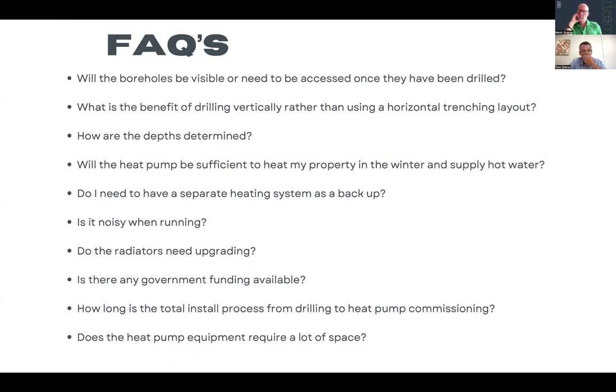So that's everything that I can say. You can see what I've got here. If anybody's got any questions about something, are the boreholes visible? They're not. They will disappear a meter below the ground. So you will see only a manifold chamber flush in the ground, which you need to have access to for servicing, to check the flow through each borehole every year.